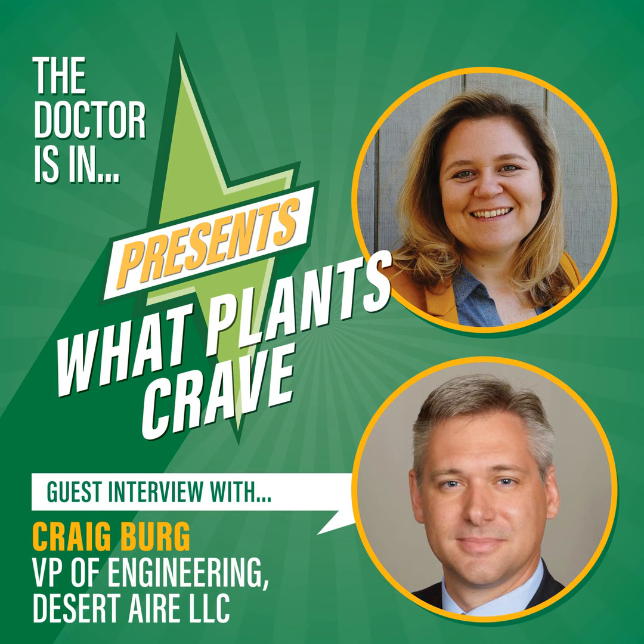I would say that's not too unusual for a system at some point to see some changes in loads, no matter what the application. I think one of the items in front of us with the indoor plant environments is that this dynamic load through time causes us to potentially size the equipment in a way where we may have more of an issue. If we oversize it tremendously, again, I don't care if it's got a variable speed compressor or if it's got multiple stages, then there's this possibility that we're doing some cycling of that compressor and the whole refrigeration system at this part load. And that can provide a little bit more risk, and it can be difficult to keep up.